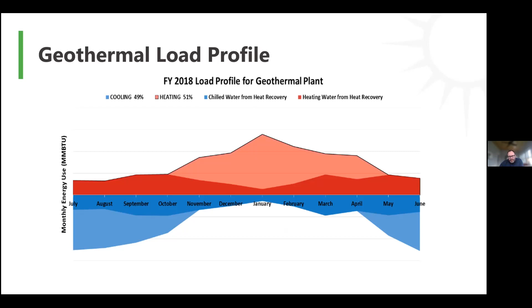I wanted to share the specifics of the coefficient of performance for that plant. This was measured in 2018, and they continue to measure it annually. At the peak of the cooling season they're achieving a COP of almost 8, and at the peak of the heating season they're still well above 3 from a COP perspective.